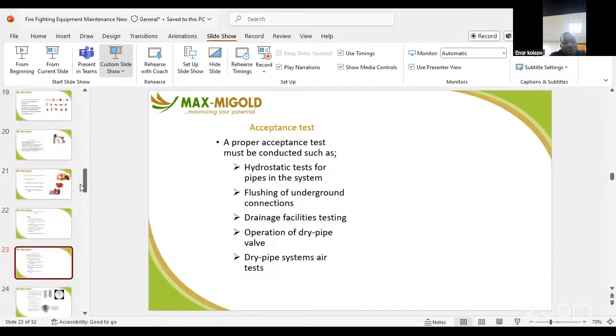In all we are doing, we should ensure that for whatever installation or maintenance is carried out, there is what we call an acceptance test, when you make the vendor or the contractor perform the test as good as it is in operation. You want to ensure that whatever data or parameters are being generated are a direct reflection of how it will perform upon usage. So when it's put to use, how will it perform? That is very key to us here.